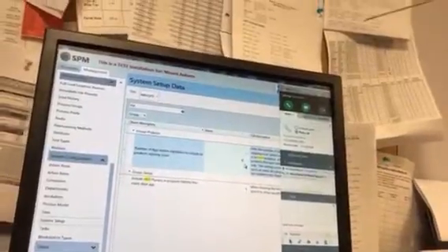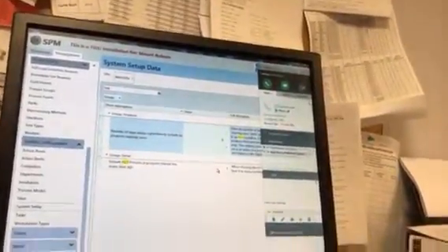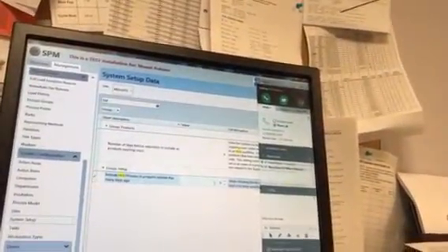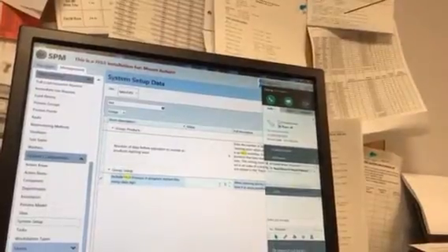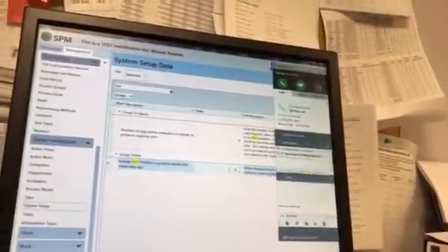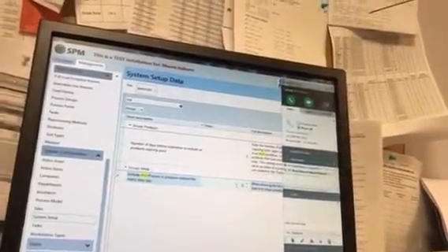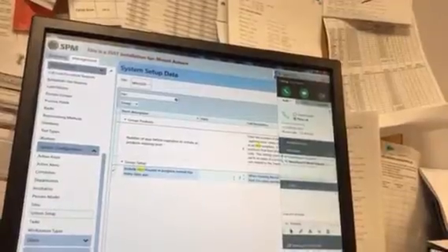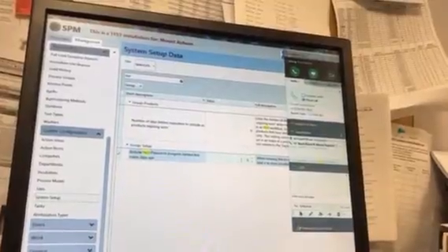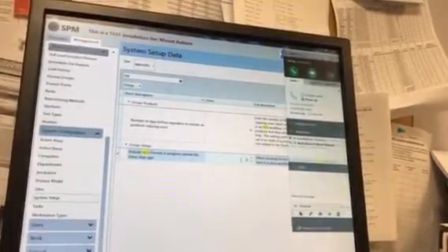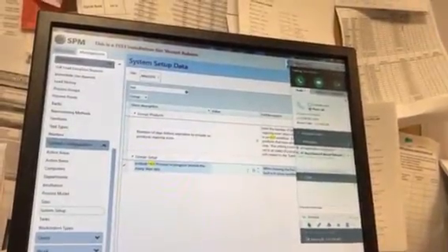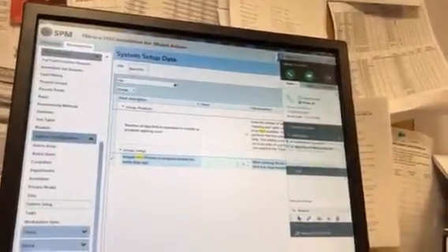Perfect. Okay, so then the only other piece is on the list of scopes that are being processed. There's two modes of it. One is what's currently in process, i.e., what's in your System 1E right now, for example. So running through it, it's in progress. Or maybe they started in the System 1E. It's on the clean side now, but they haven't finished it in the warming cabinet. So those are going to show up in there until they finish all the steps that they needed to do.